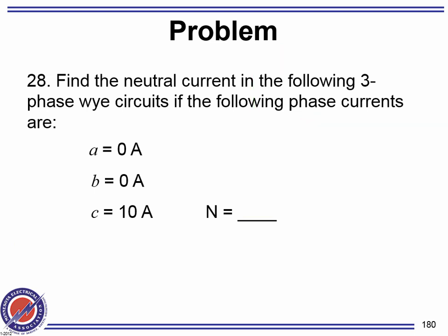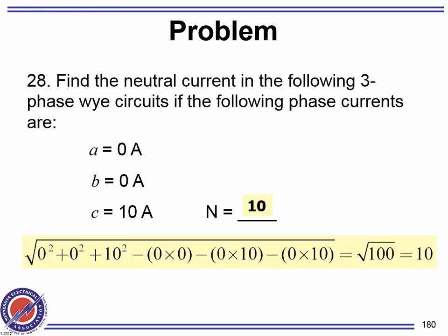That's 10. Now what happens if the two phases are off? So these are in one phase, phase A, phase B, phase C, and you turn this phase and these lights off. This is a single phase circuit. What would the neutral carry in a single phase circuit? Same current as a phase.